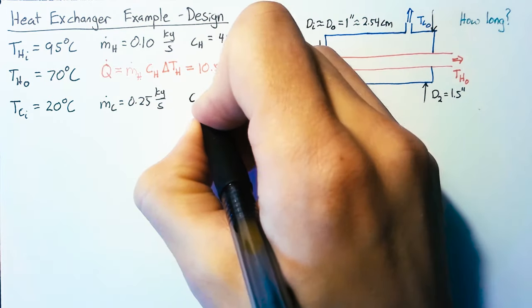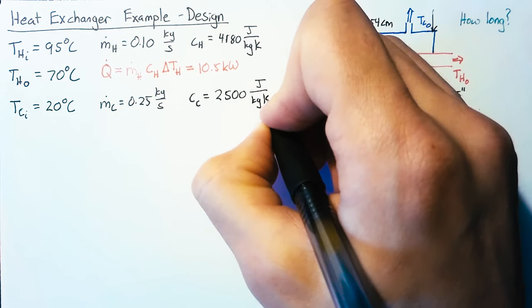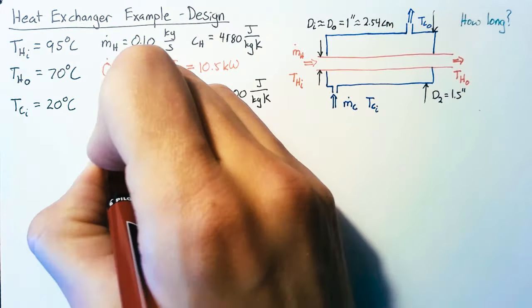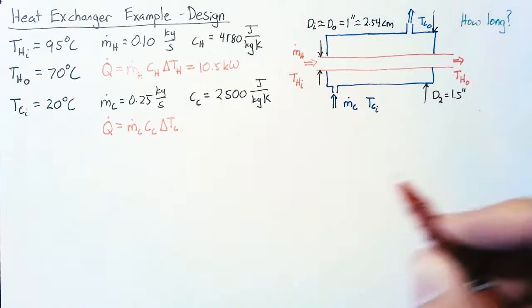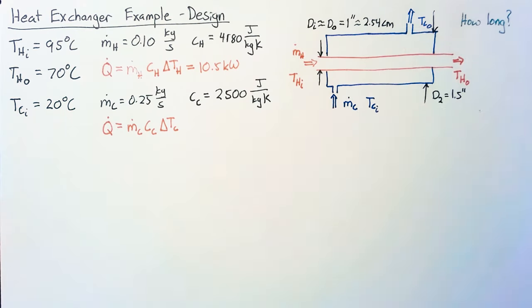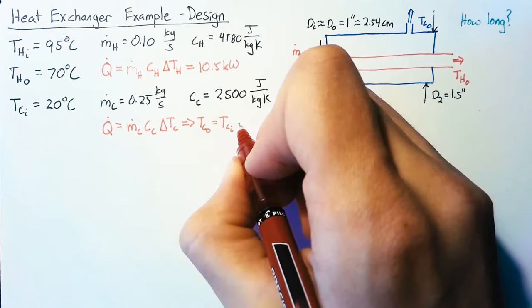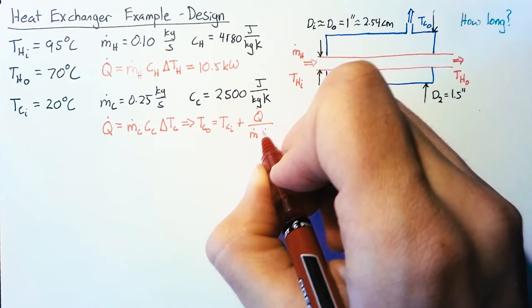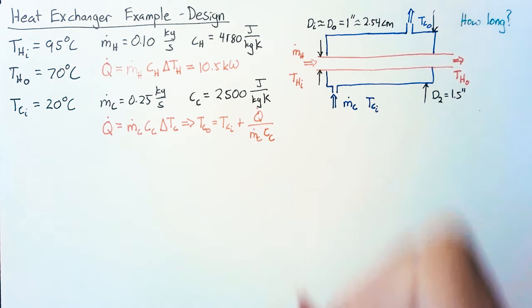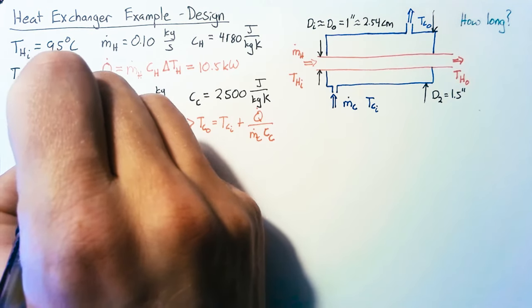Our coolant also has a specific heat, which we'll set to 2500 joules per kilogram Kelvin. With that value we can write that same equation for the cold side. We're going to assume there's no heat loss through our outer pipe wall, so the pipe is well insulated. We can rearrange to find T_c_out = T_c_in + Q_dot/(m_dot_c * c_c). Plugging in our values, we end up with T_c_out of 36.7 degrees Celsius.